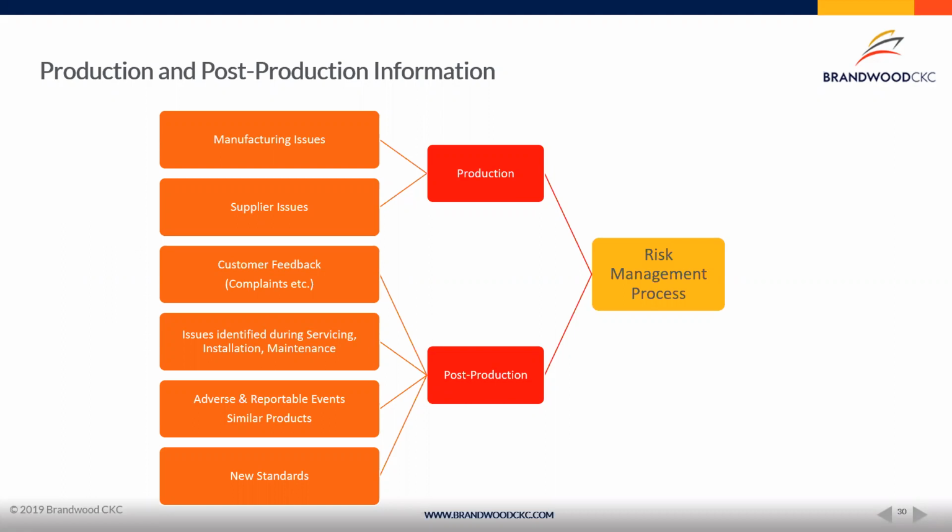You do your risk analysis, you go through the controls, you look at residual risk, and so on and so forth. So I'll continue to push on it, but the biggest thing that you can take away from this is that this is an iterative process: after design and development, you're not complete. You continue to bring these things back into the process and ensure that the risk of your device is lower than the benefit that it creates.